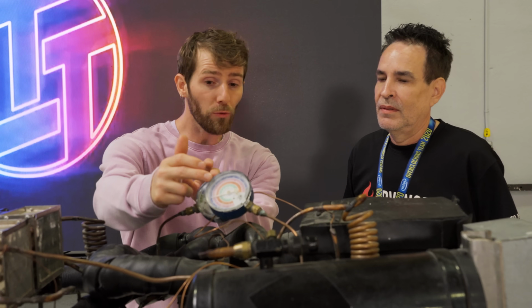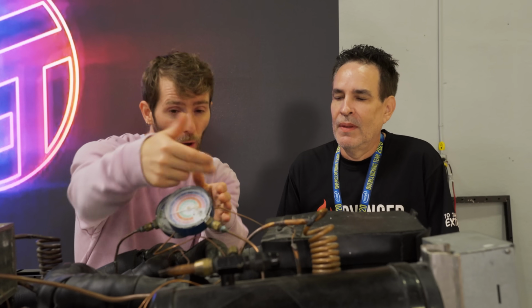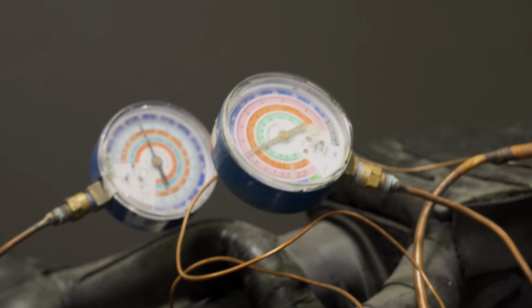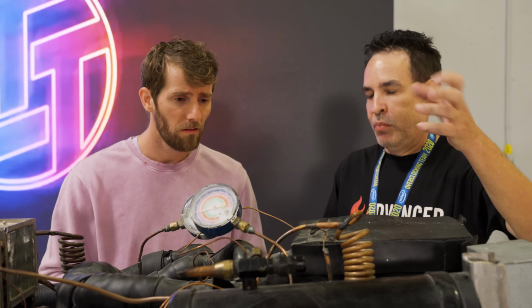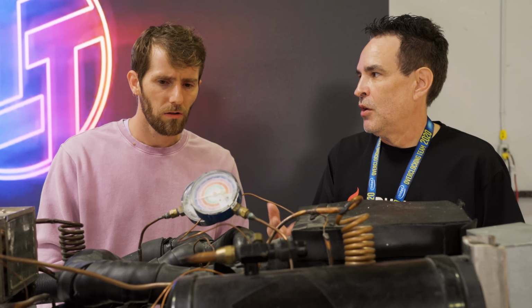There is one thing we missed. Do I need to be paying attention to these? If these go to the red line, do I freak out and pull all the plugs out? No, these just let me know if the second stage and first stage are running. So if my pressures go up, I can pull the plugs. When we shipped it, like when you took the picture, I can know if the gas has leaked or not. In the future, we can mark the pressures now, and a year from now see if we lose some pressure, and recharge the system.